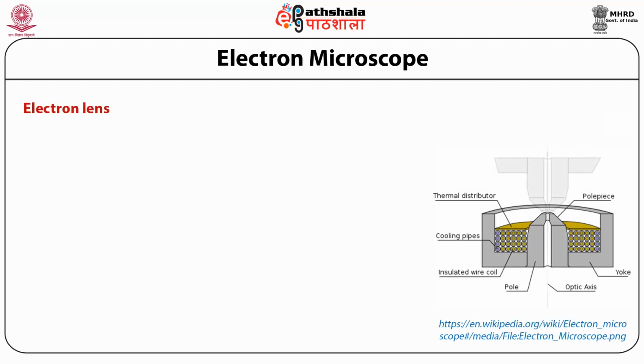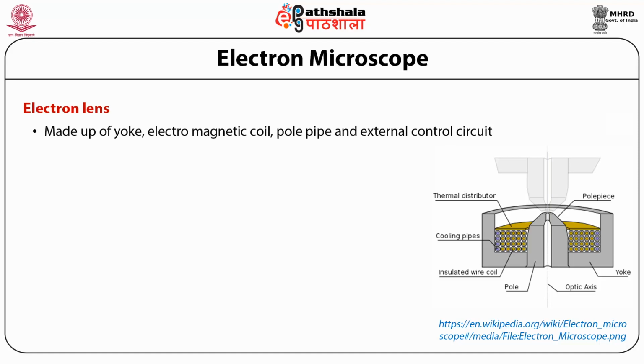Electron lens. So the microscopy lens through which the electron beam is passed is very critical for the resolution as well as the contrast of EM imaging. It is actually made up of a yoke and electromagnetic coils, pole pieces, and an external control circuit, as shown in this picture. The electromagnetic coil generates a convex lens-like configuration so that we can magnify the image.